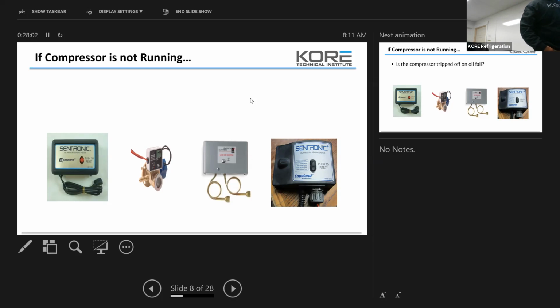This is a mechanical one. This is the one I was talking about. It looks for a differential across the crankcase and the pump. So the actual low pressure in the compressor, to make sure that you have oil pressure there in the pump. If you drop below a certain threshold, I think it's 12 PSI or 8 PSI, depending on the compressor, it's going to trip the compressor out. It's going to say, you don't have enough oil pressure to continue to lubricate the compressor. We're going to shut it down until we fix whatever condition is causing us not to have lubrication in the compressor, so we don't damage the inside of the compressor.